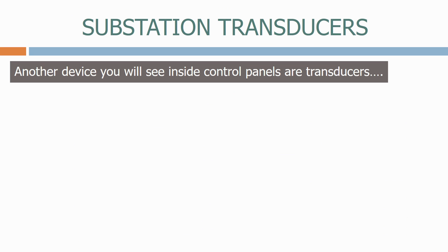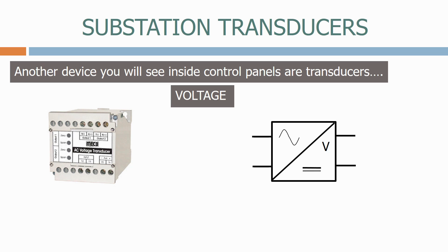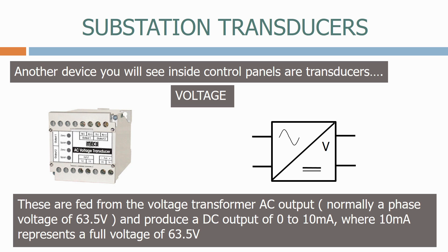Another device you will see inside control panels are transducers. The first type is a voltage transducer. Here's the symbol we normally use. These are fed from the voltage transformer AC output, normally a phase voltage of 63.5V, and produce a DC output of 0-10mA, where 10mA represents a full voltage of 63.5V.